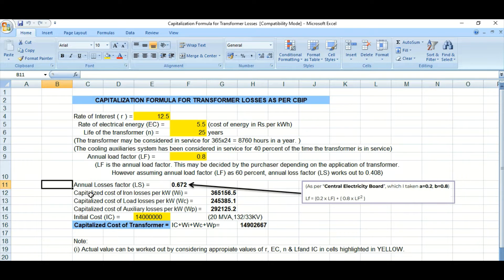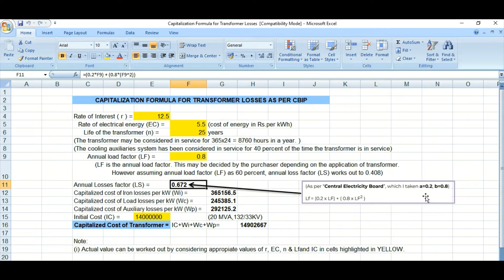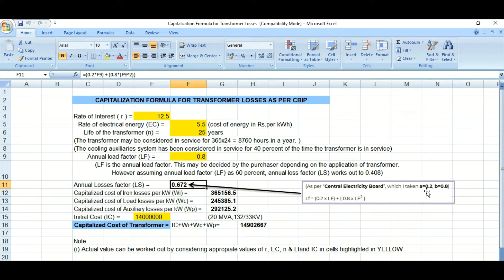The first result is the annual loss factor, denoted as LS. As per the Central Electricity Board CBIP standard, the constants are A = 0.2 and B = 0.8. The formula is: LS = 0.2 × LF + 0.8 × LF², where LF is the annual load factor. This formula is derived from the CBIP standard.